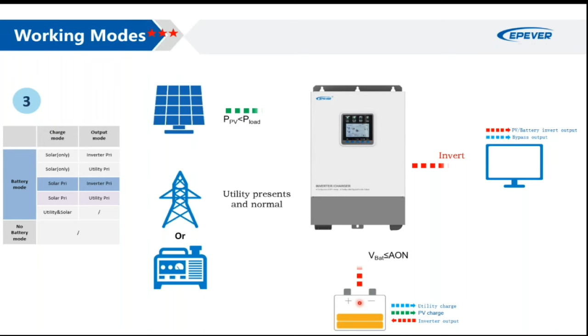Then we have the solar priority mode. So you say that it's a priority for me that solar charges my battery, and inverter priority says that my priority is that the inverter provides power to the consumers. So in case you don't have enough PV power, the battery will be consumed, and it will reach a moment where the voltage is low enough that it will not be able to provide the power to AC consumers. So the battery and the PV will together power the load.